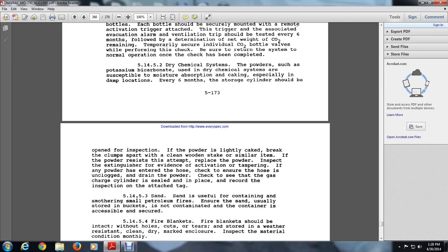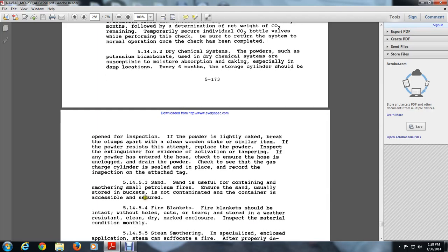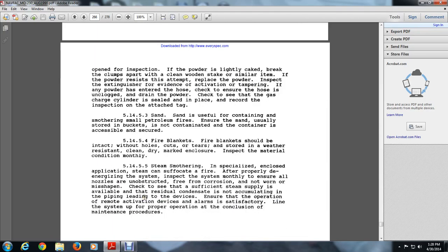5.14.5.3 sand. Sand is usually used for smothering small petroleum fires, ensuring the sand is usually stored in buckets, is not contaminated, and the container is accessible and secured. 5.14.5.4 fire blankets. Fire blankets should be intact without holes, cuts, or tears, and stored in a weather-resistant, clean, dry, marked enclosure. Inspect the materials' condition monthly.